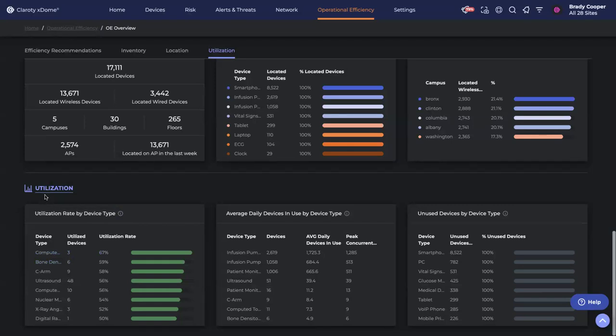If we're seeing data from a specific C-arm across the network via span, we take that into consideration, as well as integrating with your DICOM servers and pulling that metadata out. We don't pull any patient sensitive information out of those servers or images. It is specific to the device and the device activity. And that's how we build these pictures of these devices and these utilization graphs.